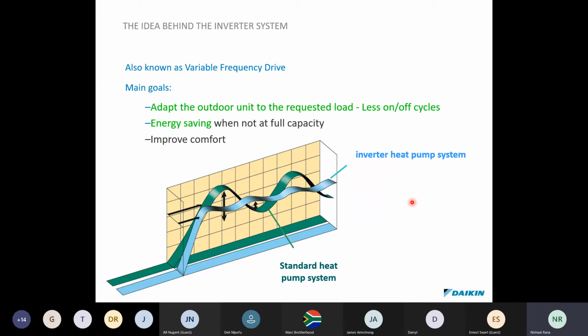But with the VFD, obviously you can accurately control how much duty or how much work you need to have done for the exact point. So you could be, for example, at a 55% load, and then your next load could be at 77% load. With the variable frequency drive, your tolerance factor is maybe about 1% or 2%, and you get exactly the amount of duty that you need. And obviously, the main purpose of inverter control is to save on energy and improve on the comfort. Because the worst thing sitting under a cassette unit or a diffuser is that all of a sudden the expansion valve opens and you get a dump of cold air into your coil and you freeze, because you probably have air hitting you at about 14, 15 degrees and it becomes very uncomfortable.